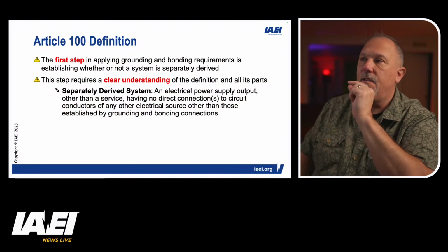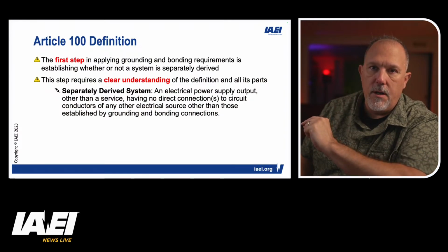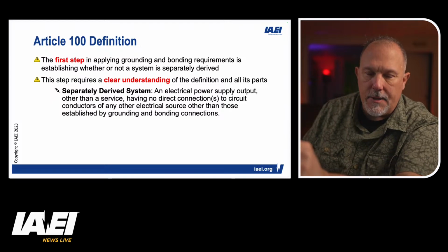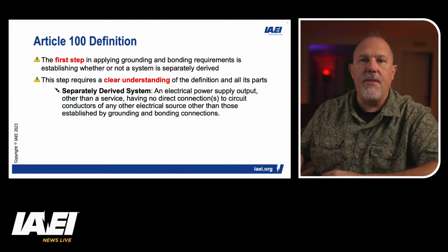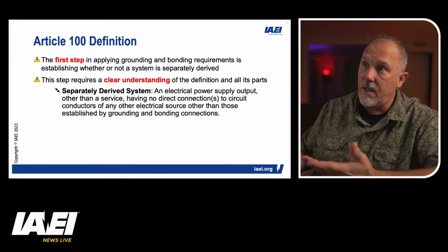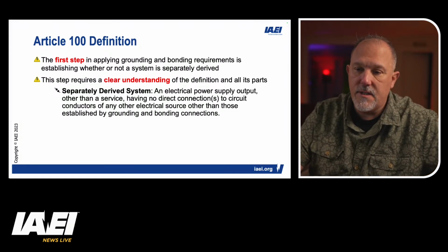If you look at that generator and you say, this is a generator, does it meet the definition of a generator? Yes, it does. You're over in 445, chapter 4. Transformers, etc. We have defined terms, and that's your gateway to what your requirements are. Separately derived systems are no different. We have to understand the defined term, identify it in a power distribution system, and then we apply the rules, in this case, for separately derived systems.